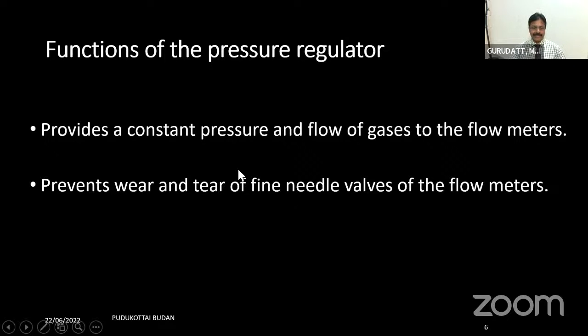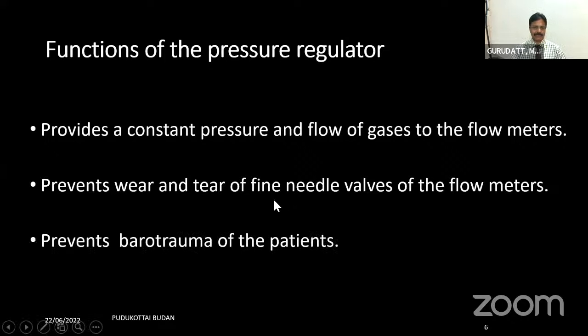The second most important function of the pressure regulator is that high pressure gases, if they directly enter, may produce wear and tear of the fine needle valves of the flow meters, and also they can damage the other finer equipment inside the machine. That also is prevented by the pressure regulator. The third thing is, it prevents barotrauma for the patients.